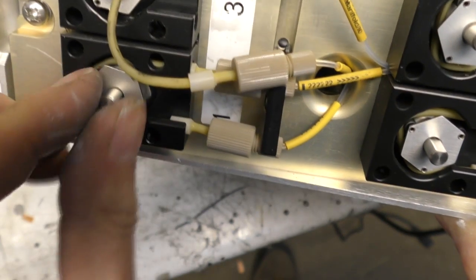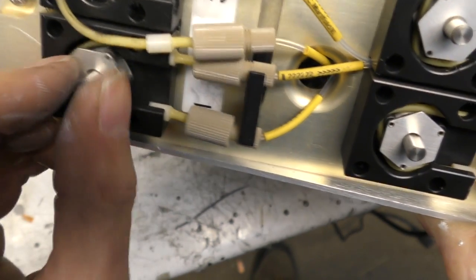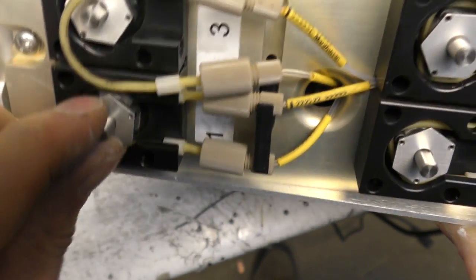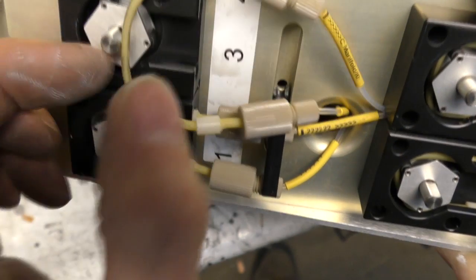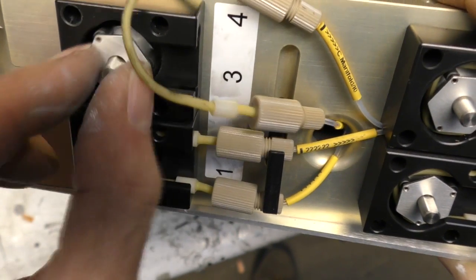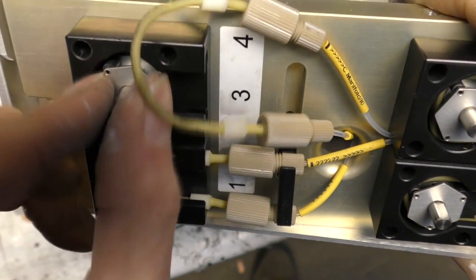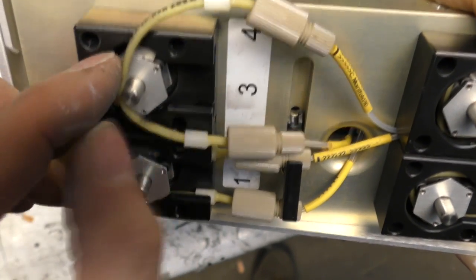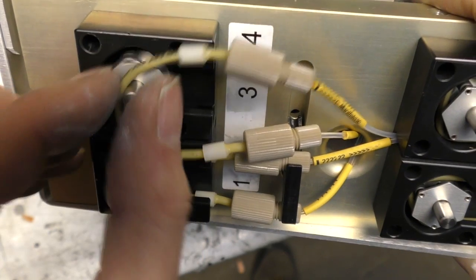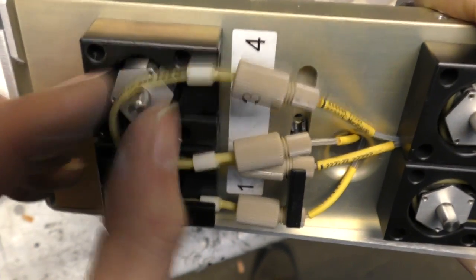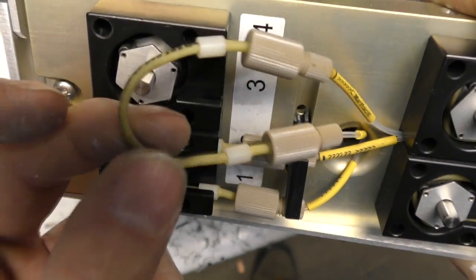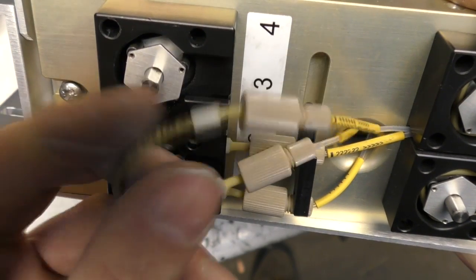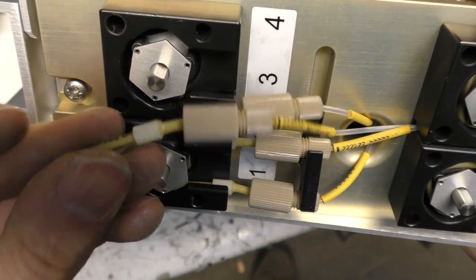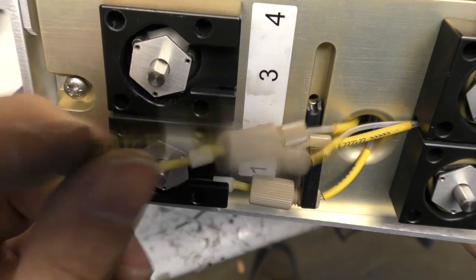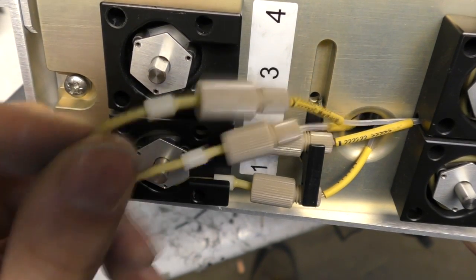It's very commonly used on medical and lab equipment because the roller is rolling a precise amount round. They pump a very predictable amount of fluid through on each step of the motor. So they're quite commonly used where you need to dispense an accurate amount of fluid, but also the only thing in contact with what it's pumping is this tubing. So you can choose different types of tubing to be compatible with whatever material you're pumping, and you can replace that quite easily if you need to.